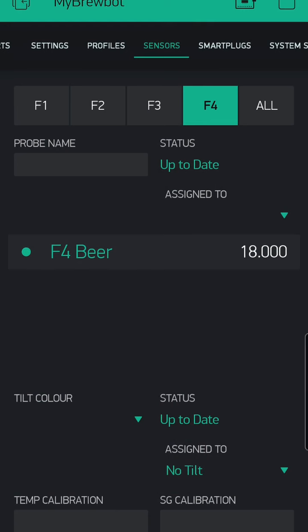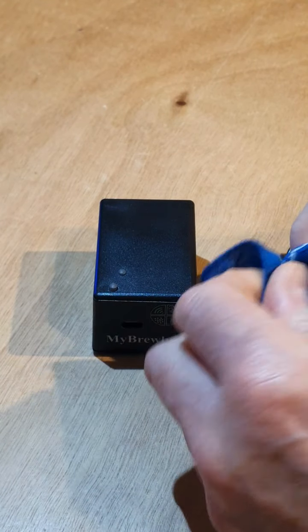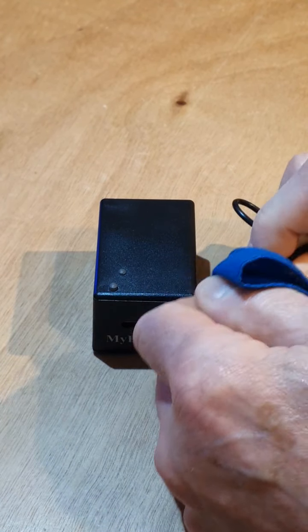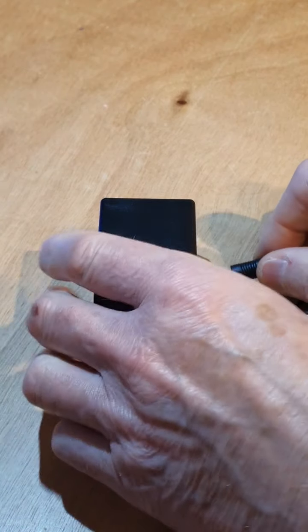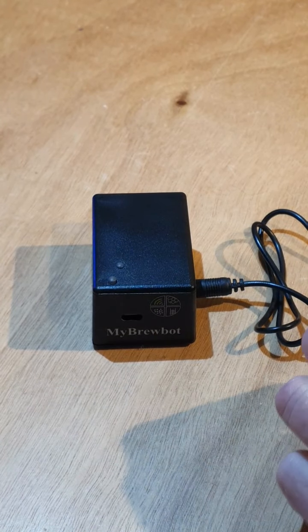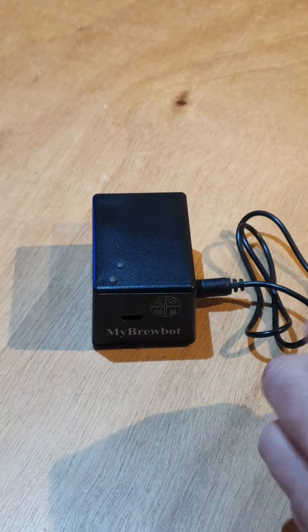Probe care. Sometimes you may see a temperature reading of 85 centigrade or 185 Fahrenheit. This is the probe telling you that it may have a faulty connection. If this happens, then power down the controller. Remove all jack plugs from the controller and hubs. Clean the plugs with a dry cloth. Reinsert the plugs, making sure they are all fully seated, and power up the controller.